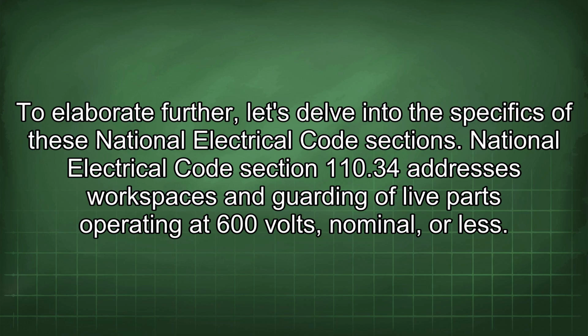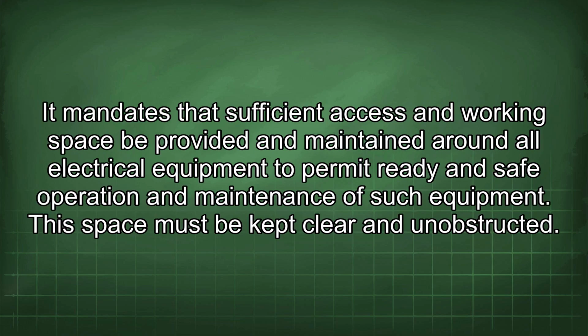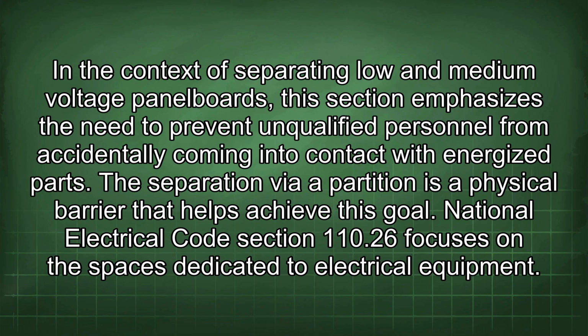National Electrical Code Section 110.34 addresses workspaces and guarding of live parts operating at 600 volts, nominal or less. It mandates that sufficient access and working space be provided and maintained around all electrical equipment to permit ready and safe operation and maintenance of such equipment. This space must be kept clear and unobstructed. In the context of separating low and medium voltage panel boards, this section emphasizes the need to prevent unqualified personnel from accidentally coming into contact with energized parts. The separation via partition is a physical barrier that helps achieve this goal.